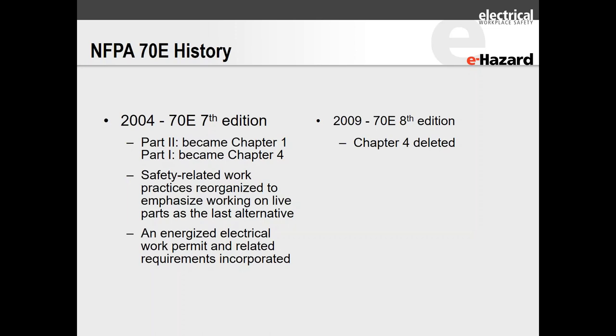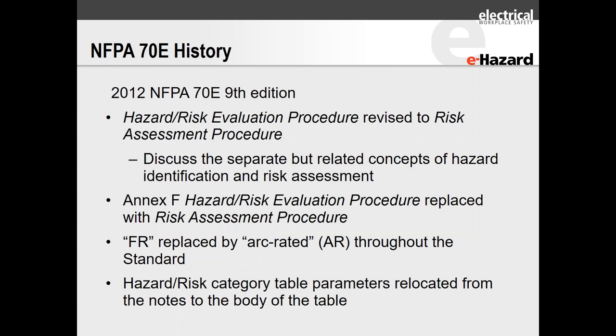In 2009, the eighth edition, chapter four was deleted — it was largely NEC content, and if you want to know what's in the NEC, go to the NEC. In 2012, the ninth edition, the hazard risk evaluation procedure was revised to a risk assessment procedure. The reason for changing the terminology was to align with international standards, using common language and bringing international best practices into North America, avoiding constantly reinventing the wheel. Annex F was replaced with a risk assessment procedure.